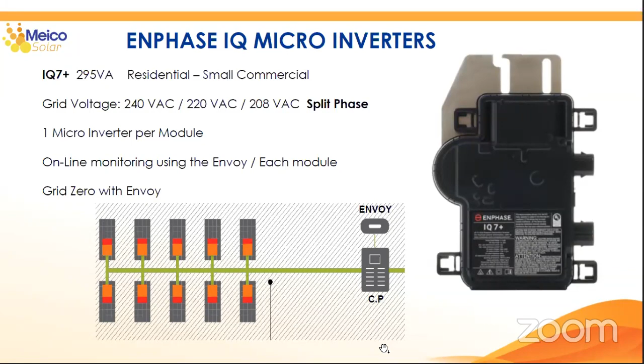This is the way you connect a microinverter. So you have the two lines, line 1, line 2, and the neutral. In this case, you don't have a neutral to connect the microinverter. It goes only to the two lines, and the neutral is only a reference for the Envoy, okay?